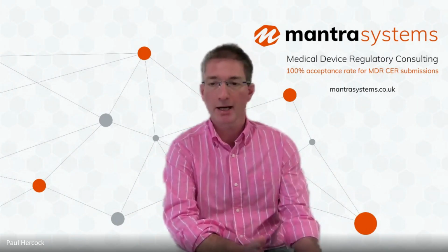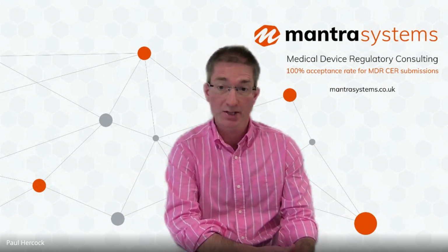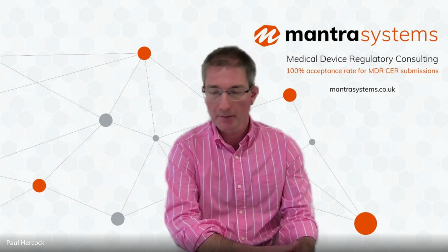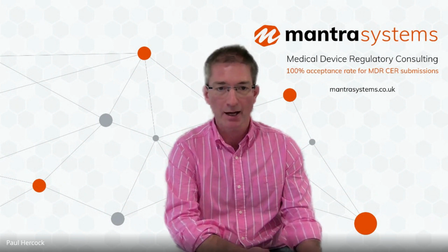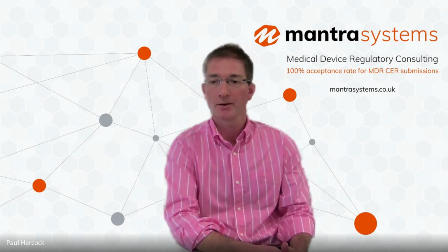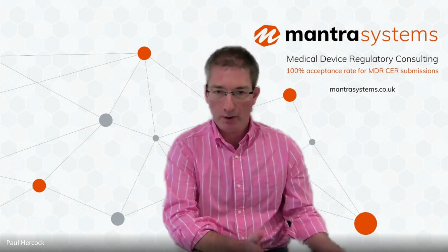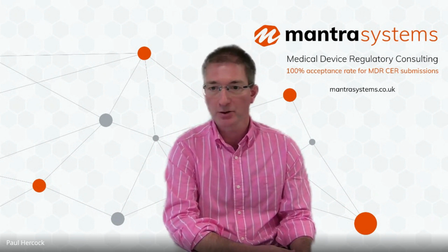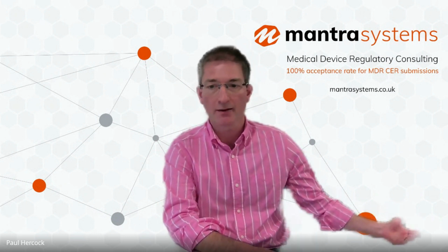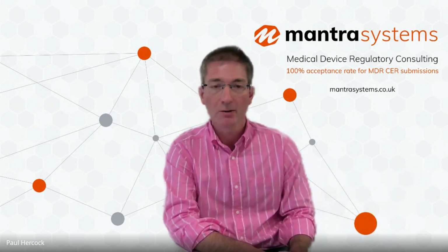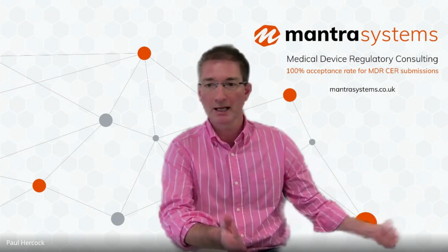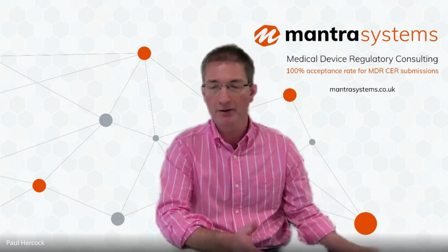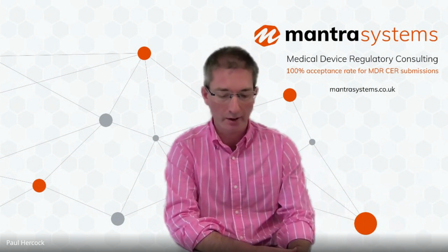The bar has been raised under the MDR for claiming equivalence. It's harder than it used to be. The fundamental reason for that was that the regulators were unhappy about a situation where, in the regulatory documentation, manufacturers were saying our device is basically exactly the same as our competitor's device, but in the marketing material, we're making claims that it's really novel and really different. So those two things aren't in line with one another.